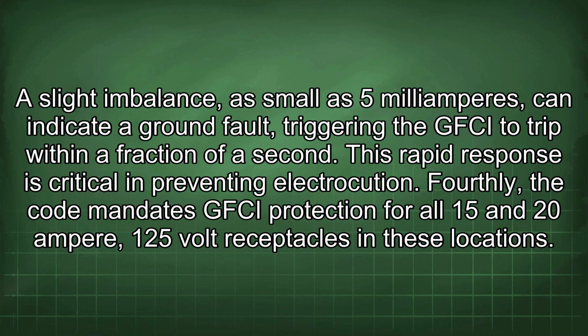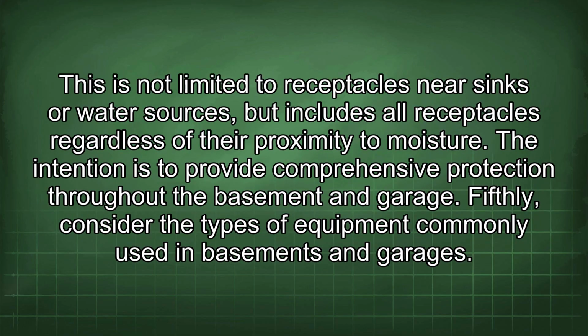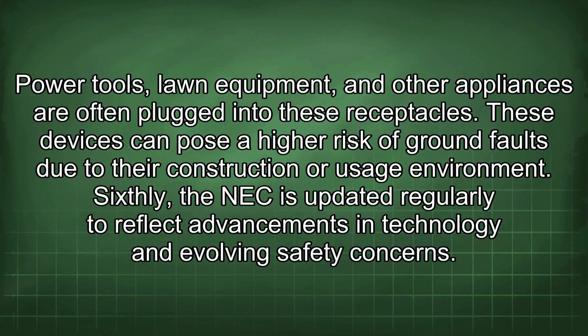Fourthly, the code mandates GFCI protection for all 15 and 20 ampere 125-volt receptacles in these locations. This is not limited to receptacles near sinks or water sources, but includes all receptacles regardless of their proximity to moisture. The intention is to provide comprehensive protection throughout the basement and garage. Fifthly, consider the types of equipment commonly used in basements and garages. Power tools, lawn equipment, and other appliances are often plugged into these receptacles. These devices can pose a higher risk of ground faults due to their construction or usage environment.